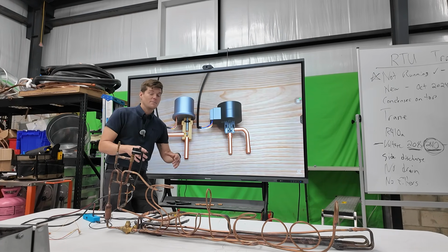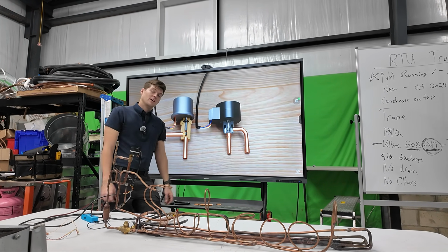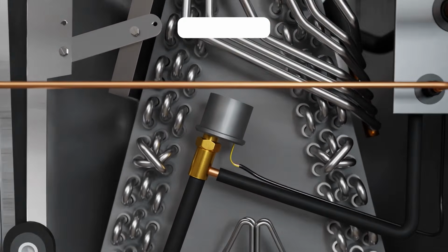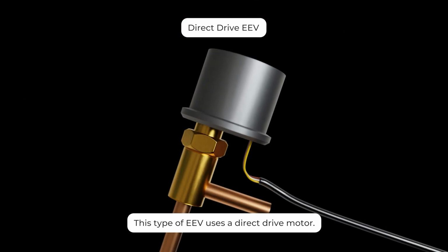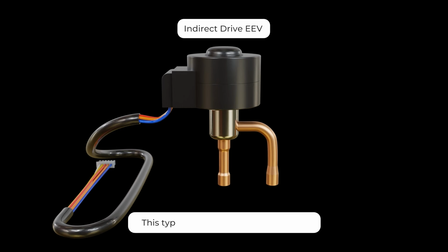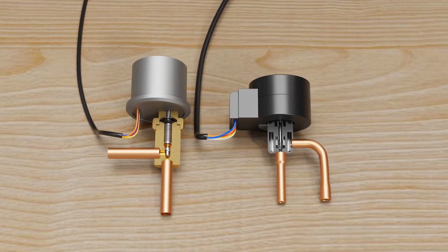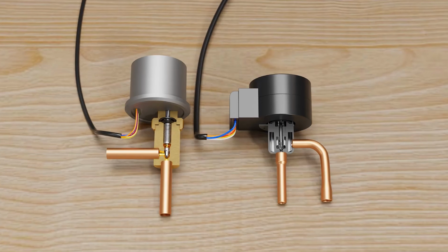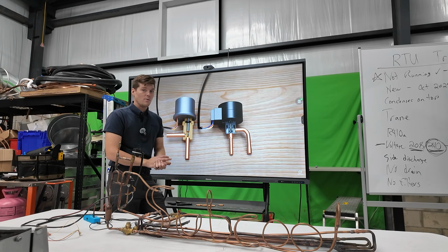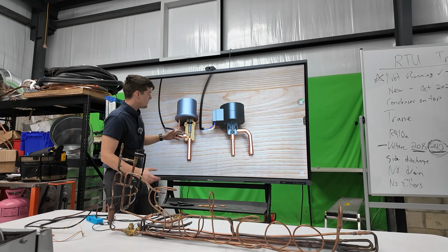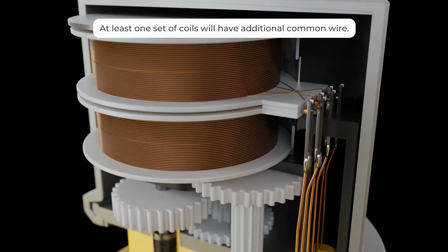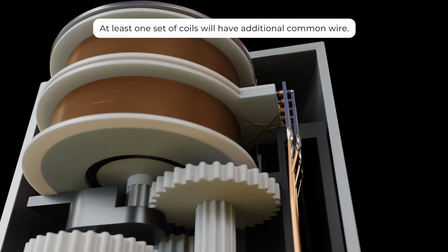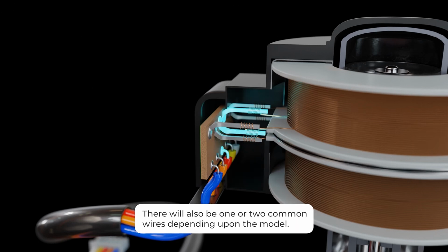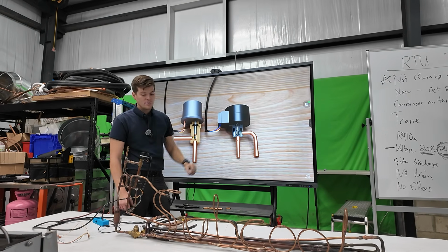Now we talked about testing it, but first let's talk about the two different types of electronic expansion valves. There's the gear-driven direct drive, and there's the indirect drive EEV. As you can see, they somewhat look similar, but from our 3D video, we break down the differences between the two and how they work. Mainly the biggest difference is that the direct drive has two commons on these windings, and this one has one, so the number of wires is 6 as opposed to 5.